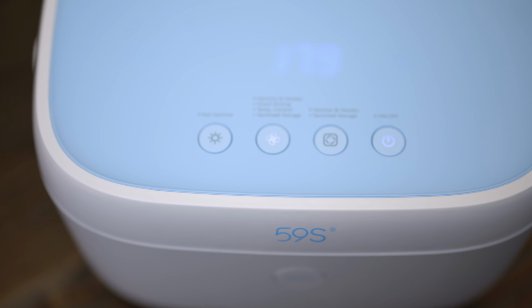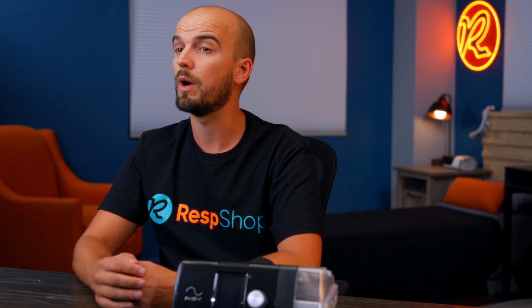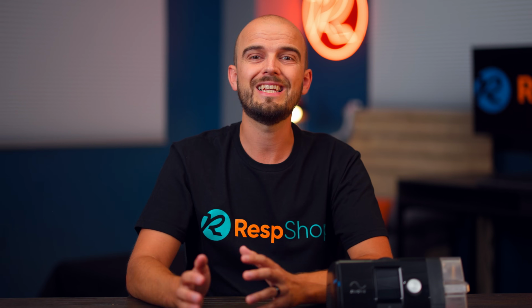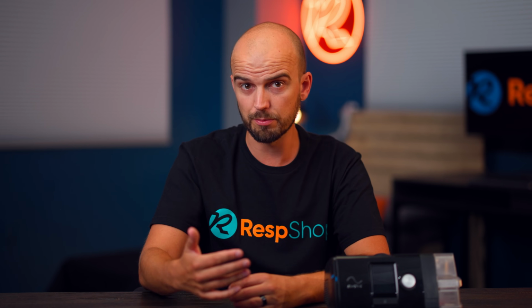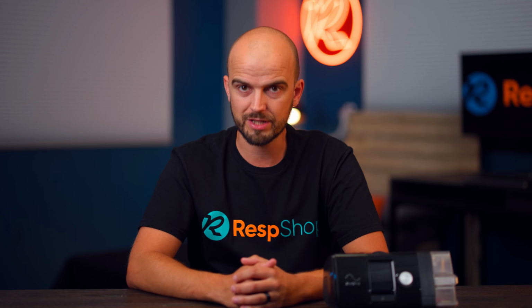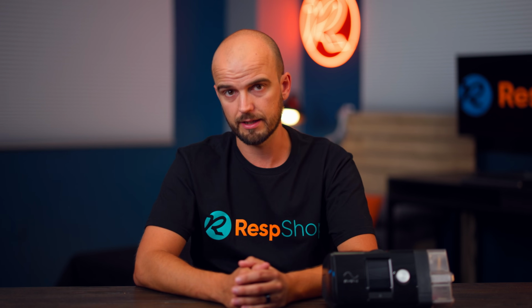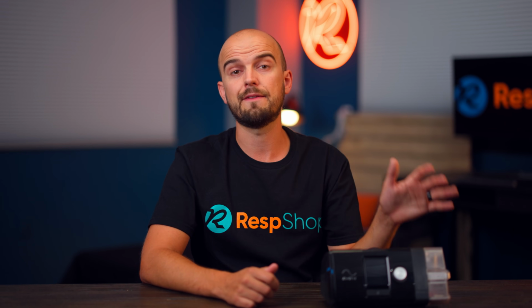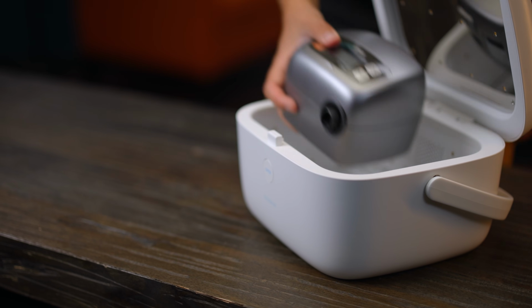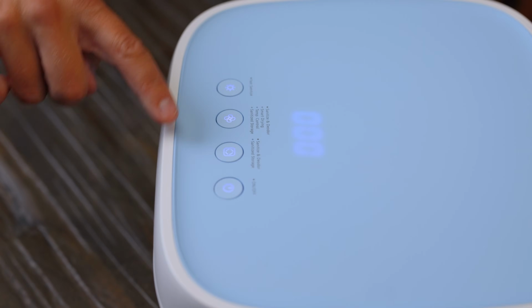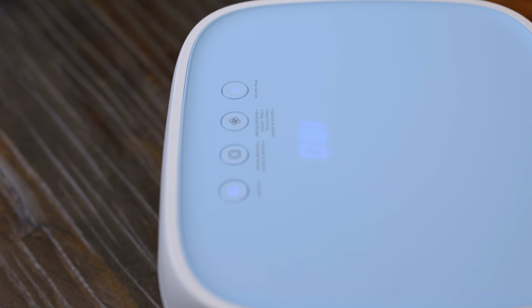This option means that you can be less concerned about making sure your cleaning process includes a sanitization step, and you can simply focus on washing away the dust and soils. Remember, the machine doesn't remove dirt from the unit, it only sanitizes, so you'll still need to remove the physical dirt as part of your routine, even if you do use a machine like this. Now your water chamber will easily fit inside the Baptizer, and smaller CPAP units might well fit as well, but if you do put your CPAP machine in it, make sure that you use the fast sanitize mode only, as the usual mode could damage the device.